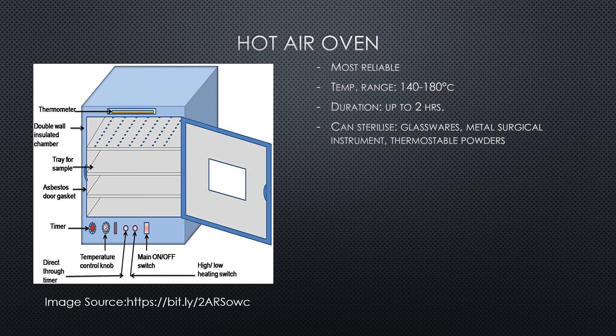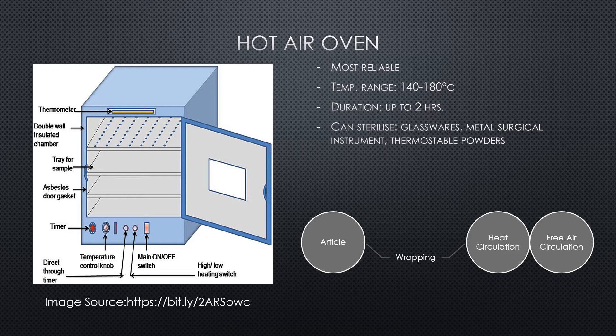A major industrial application of the hot air oven is sterilization of glass bottles for aseptic filling. This technique provides sterility assurance and also destroys bacterial endotoxins, which are products of gram-negative bacteria called pyrogens. Pyrogens cause fever when injected into the body. For depyrogenation of glass, the temperature is kept around 150 degrees Celsius.